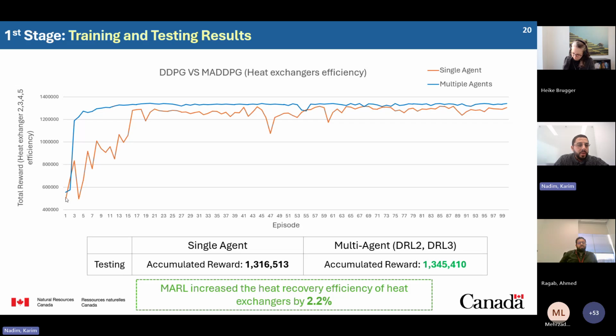These are the training results of the single agent versus the multi-agent, with the multi-agent shown in blue. As you can see, the multi-agent was able to converge to a better policy than the single agent. Here we're measuring heat exchanger efficiency on the y-axis, and the multi-agent increased the heat recovery efficiency of the heat exchangers by 2.2% compared to the single agent approach.